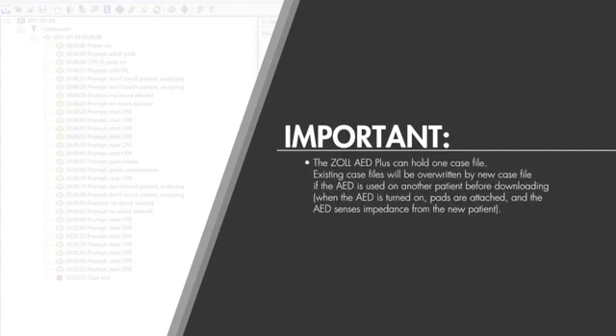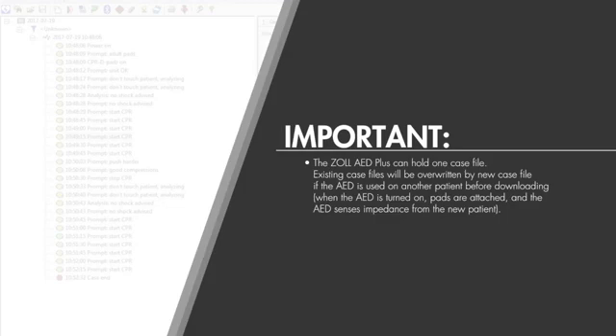The AED Plus will overwrite the previous case file when a new case file is introduced. If you turn your AED Plus on in Rescue mode and use it on another patient before downloading the current case, it will overwrite the case data and you will no longer be able to retrieve it. Be sure to download current case data before placing the AED Plus back into service.